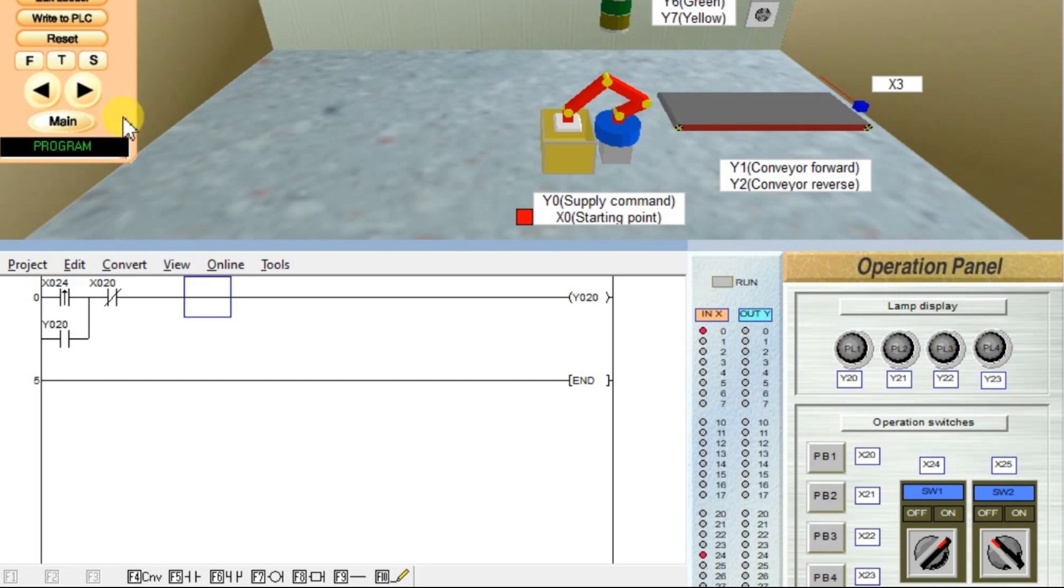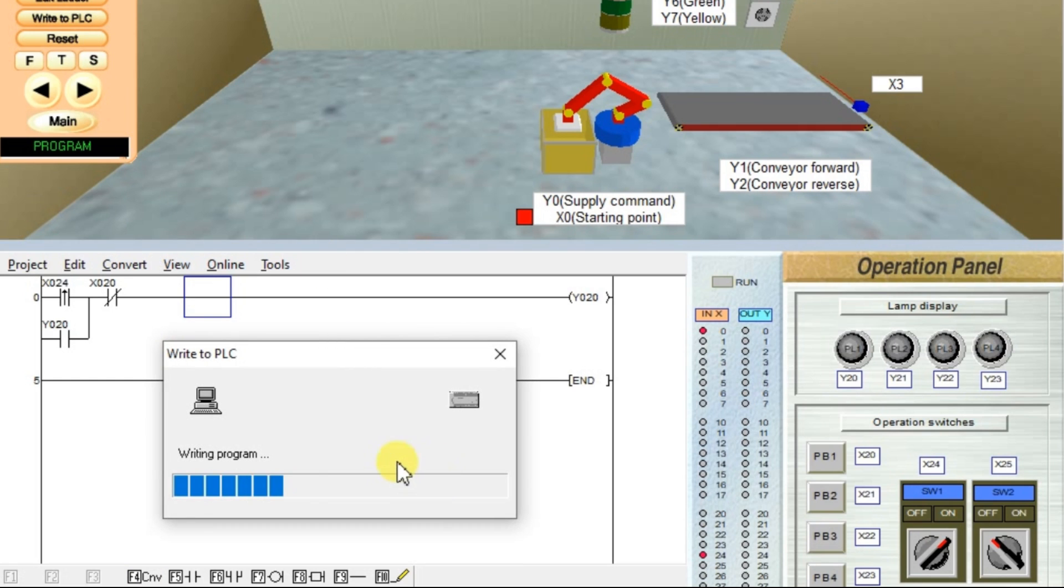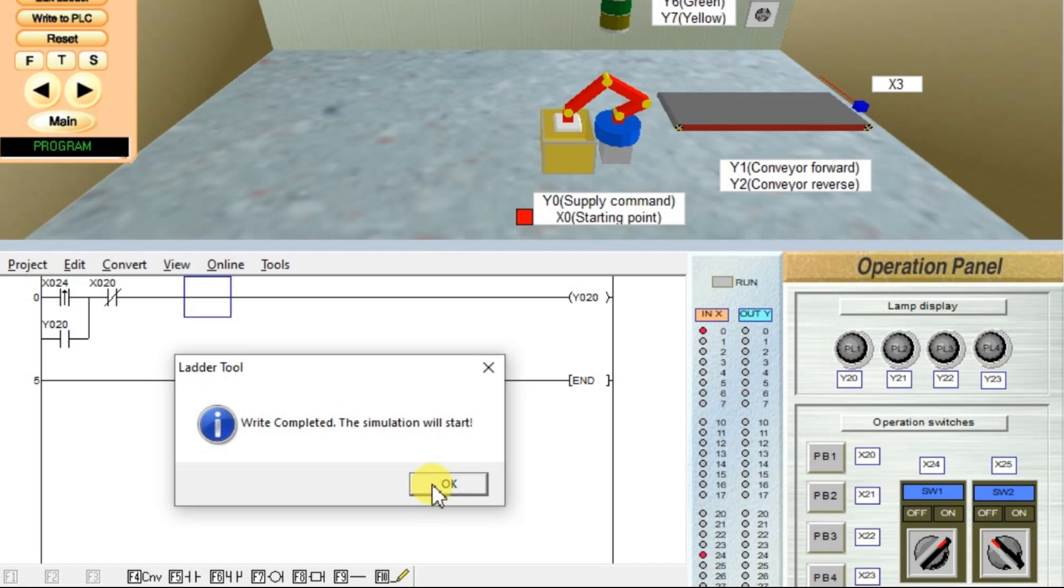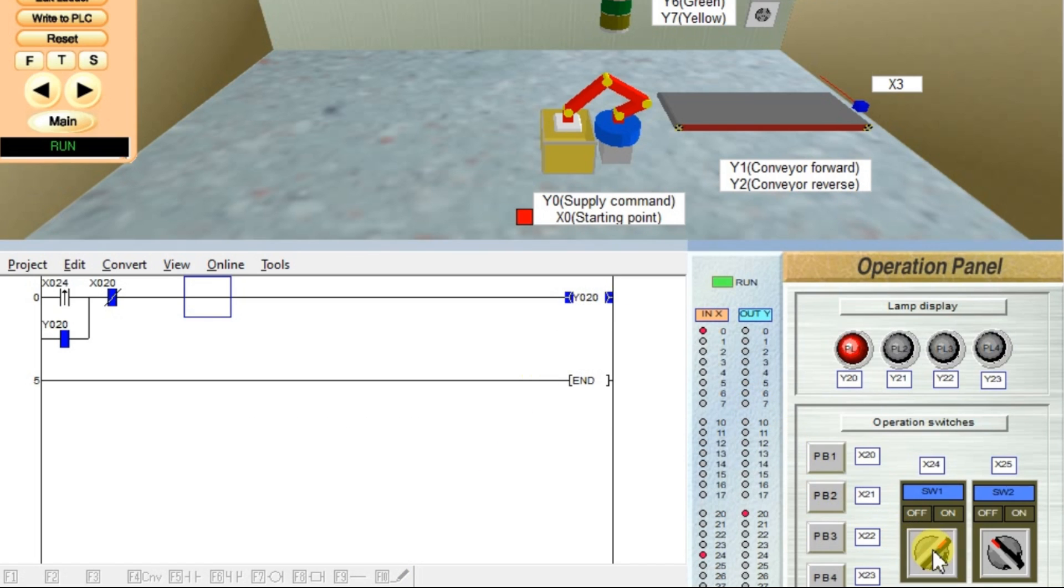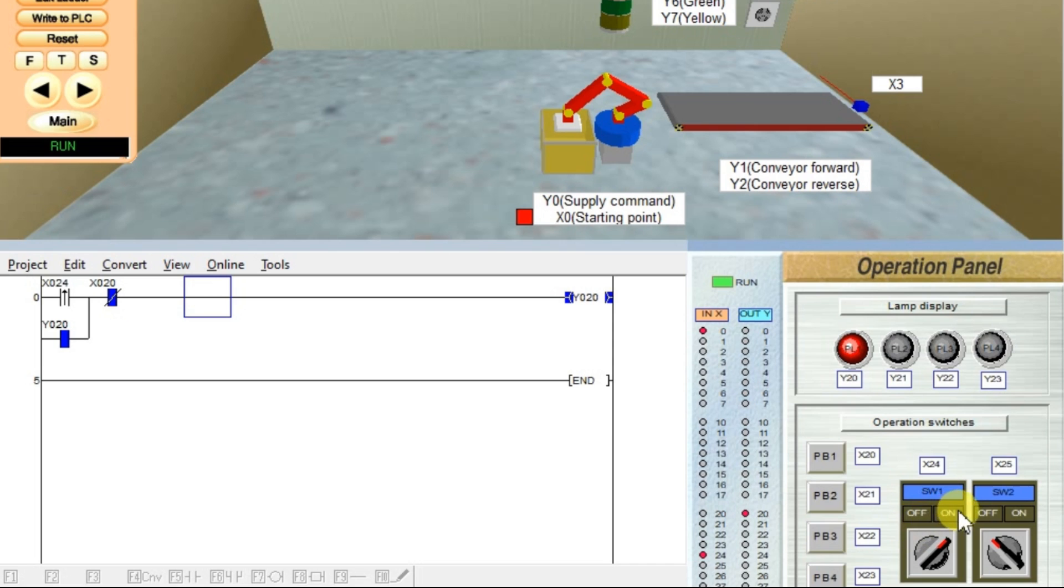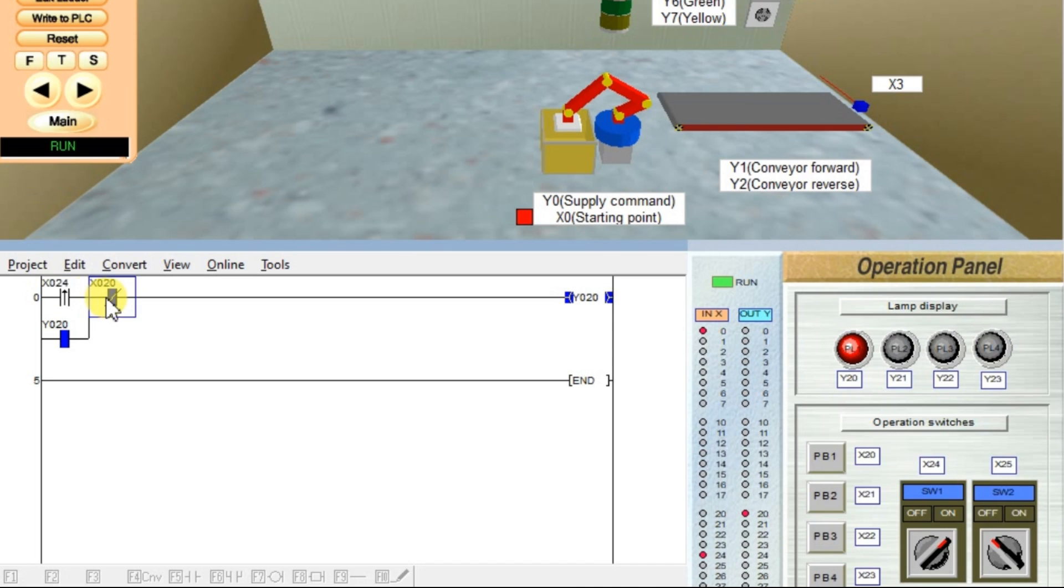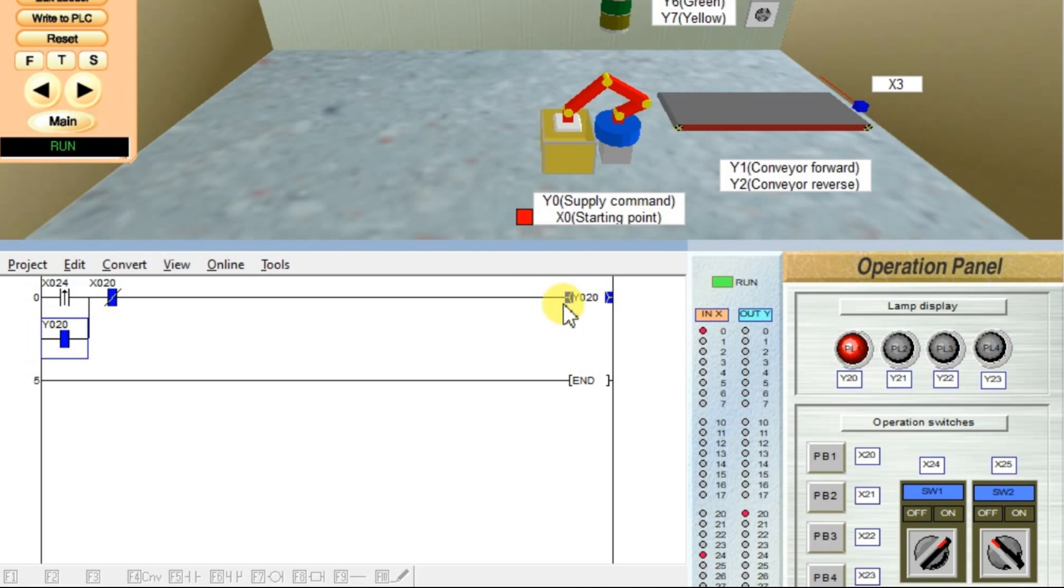Convert it. Write to PLC. Now we can able to see the output status. X24 input is ON, it is changed from OFF to ON state, so 0 to 1. It generates a single pulse. It is latched NC. That single pulse turns on the output Y20. As we have the latch, we are able to see the output status continuously.